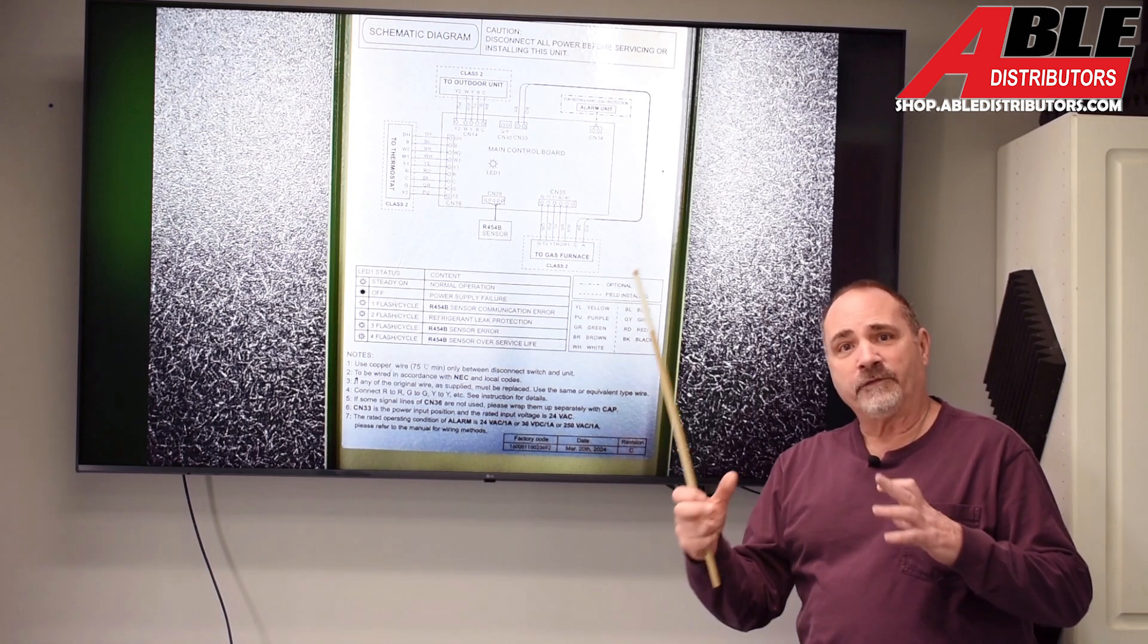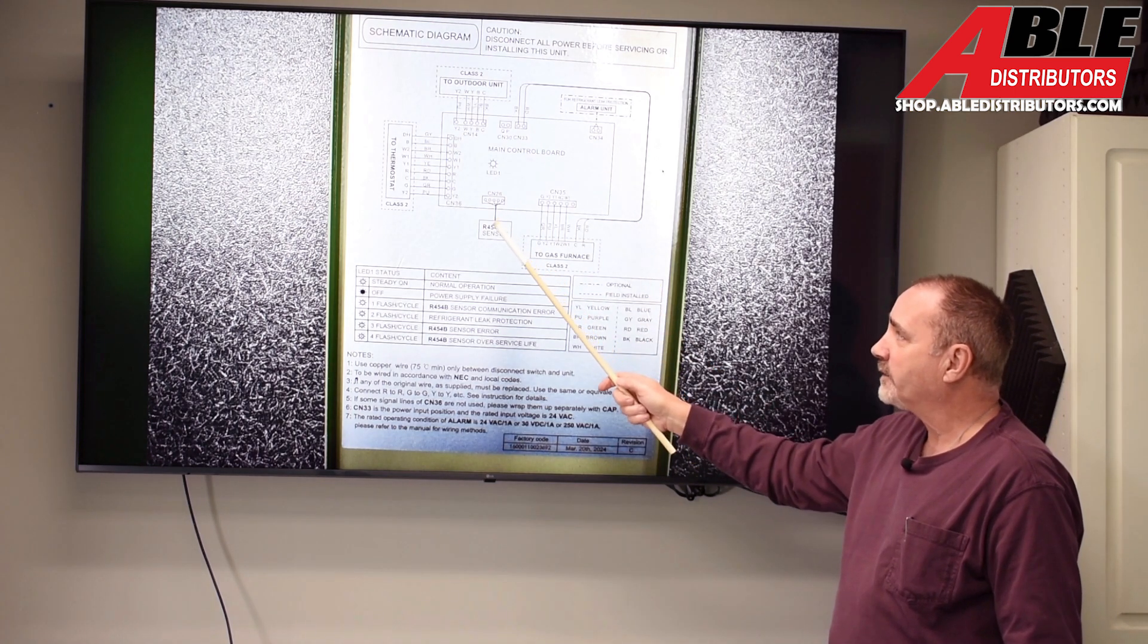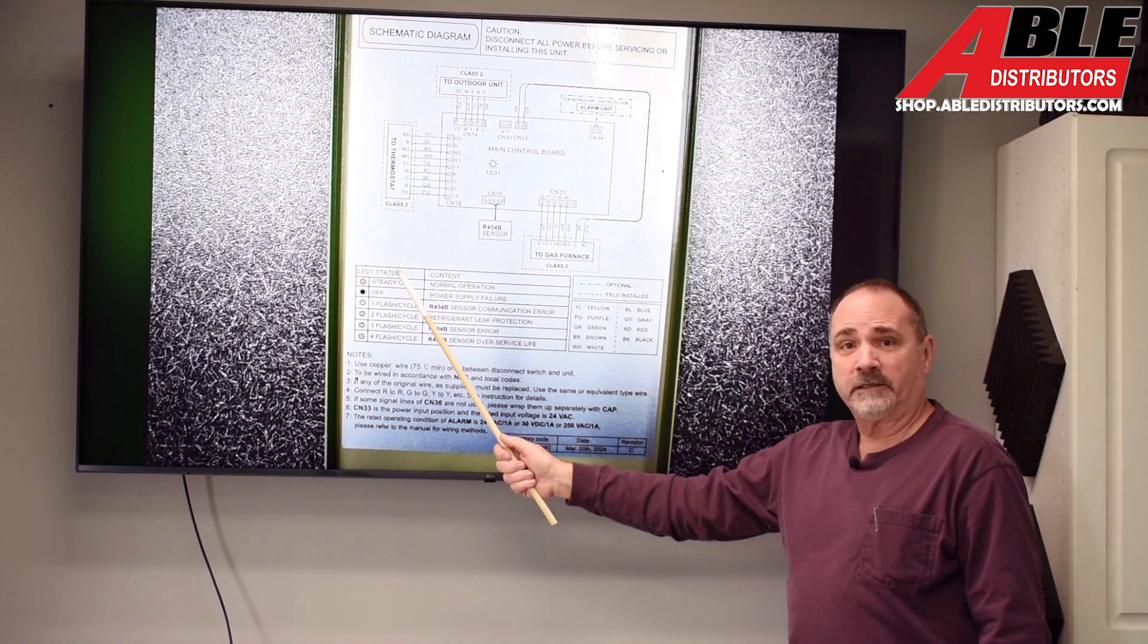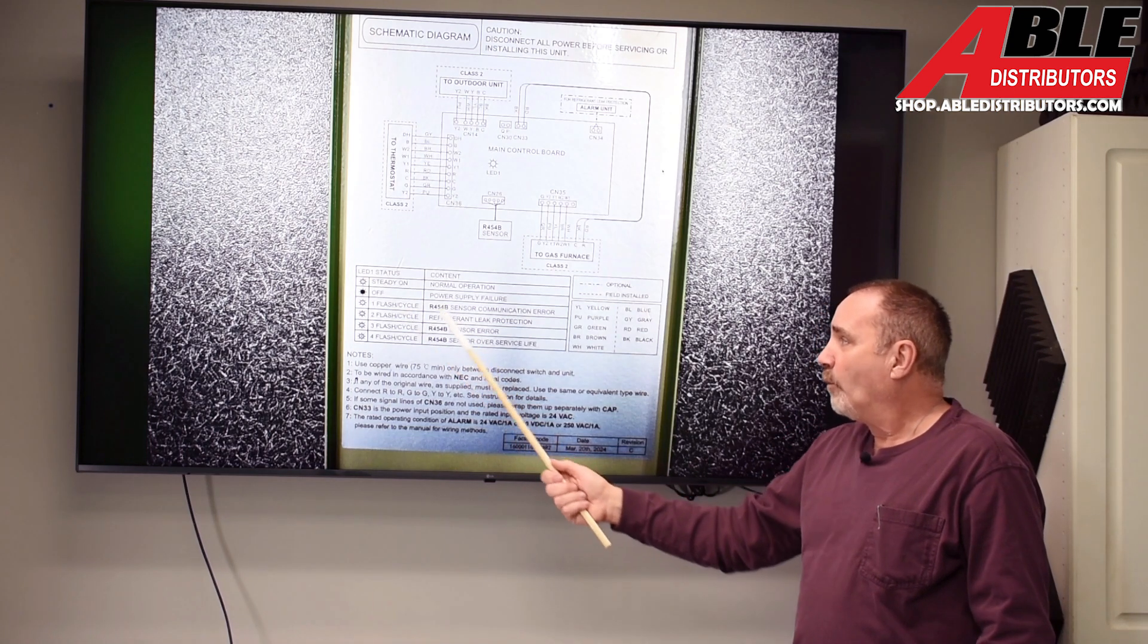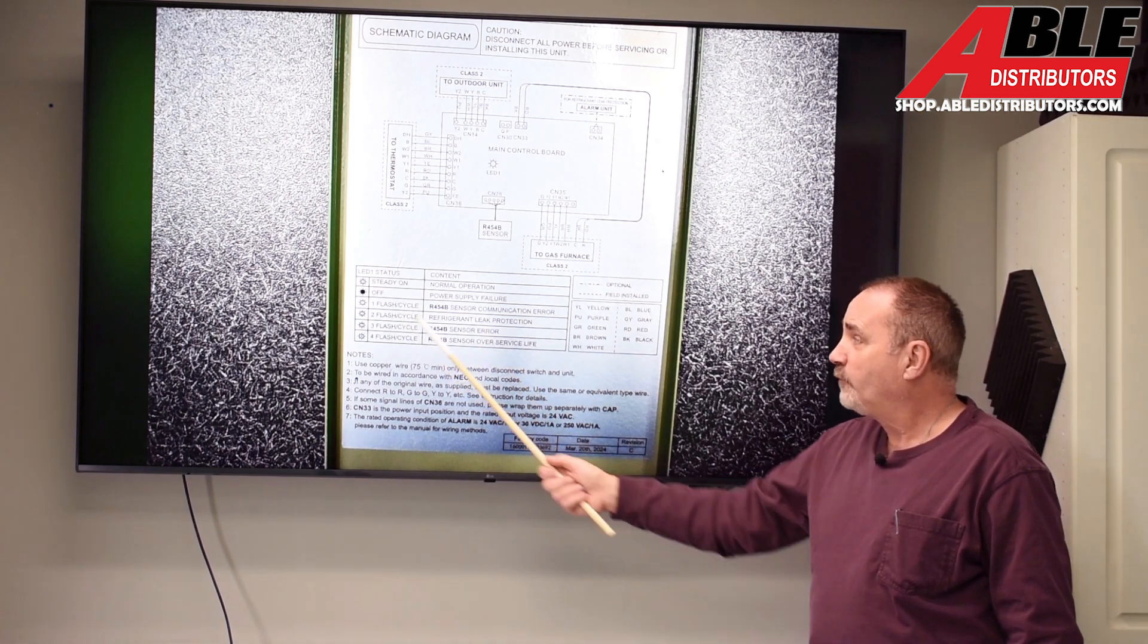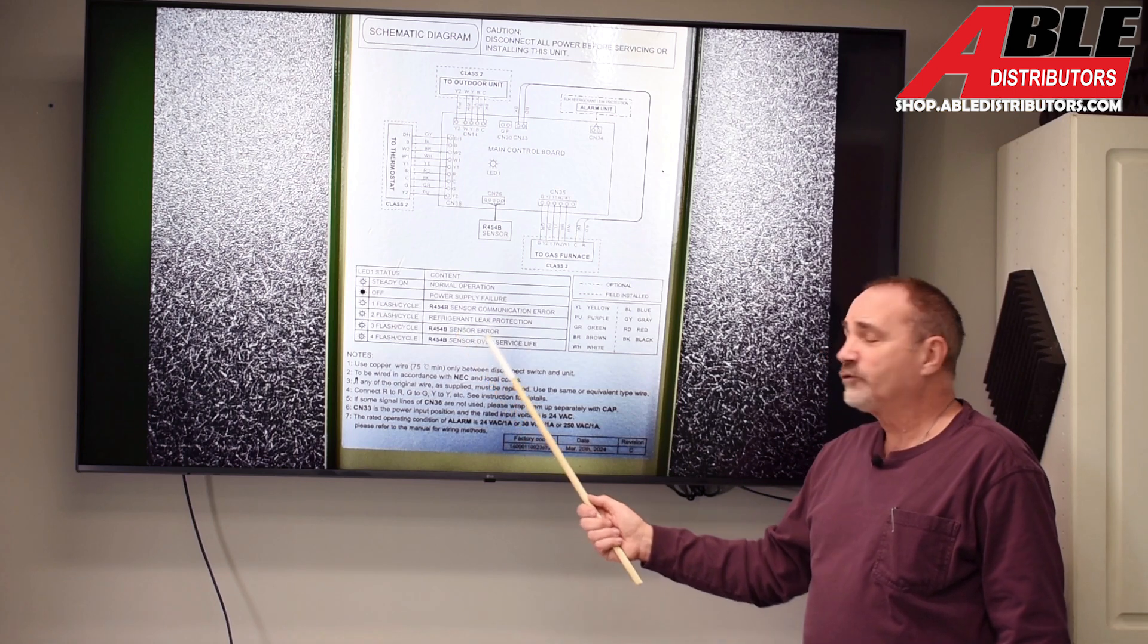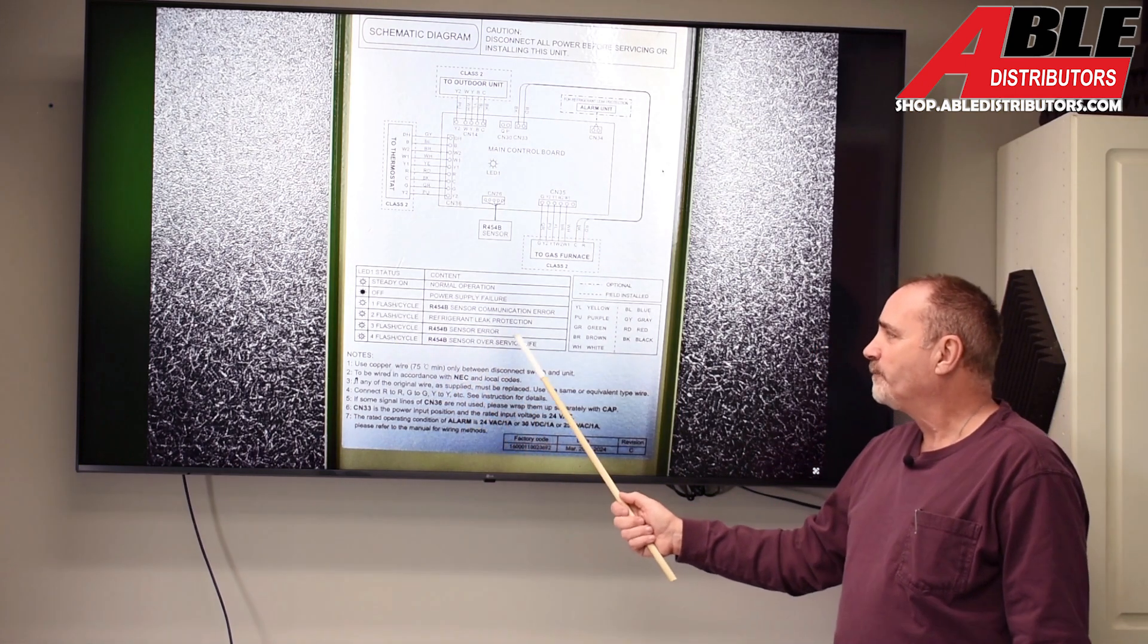Inside the lid of the interface box, you've got the wiring diagram. A lot of this you don't really need. You know where the sensor plugs in, you know what goes to the thermostat, the outdoor unit, an alarm if you want it, and to the gas furnace. But really, on the inside of here, what you're going to pay attention to is the LED status. Steady on, it's working perfectly fine. Off, there's a power problem. One flash, sensor communication error. It could be a plug, it could be the sensor itself. Two flash, refrigerant leak detected. So that's the one we're probably going to get if there's a leak inside there. A three flash, a sensor error. Again, it could be a bad sensor. It could just be a bad connection or a plug. Check those first. Four flash sensor over service life.